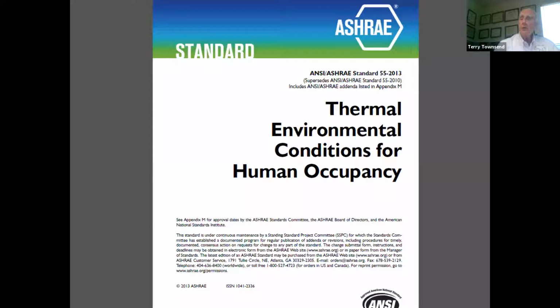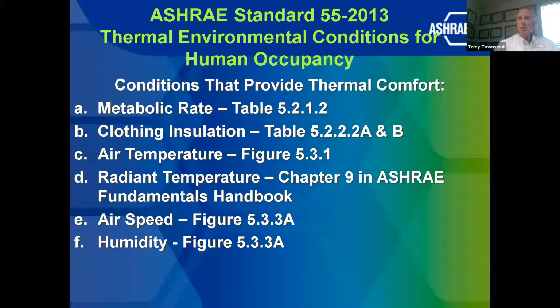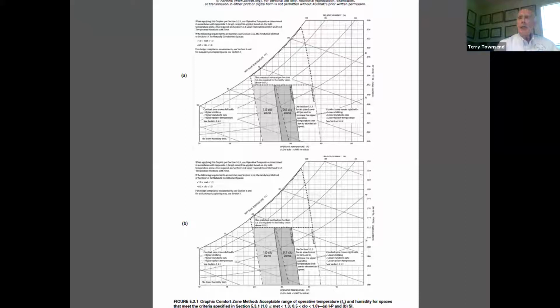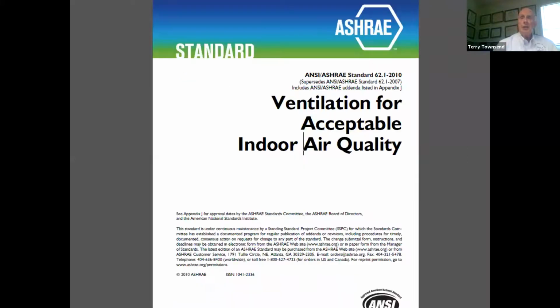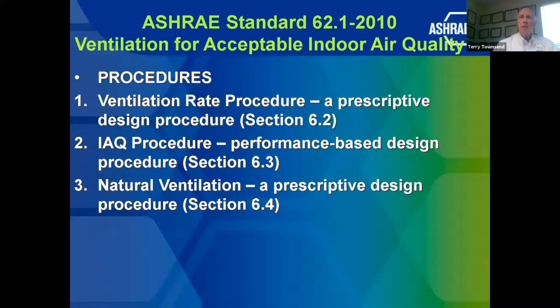First is ASHRAE Standard 55. The tables that you'll be concerned with for the metabolic rate, clothing insulation, air temperature, etc., are listed here. Most of us, I hope, are familiar with these charts that show the comfort levels we are recommended to work between for different temperature and humidity conditions. Standard 62.1 is something that most people, I feel, are familiar with, because it looks at the ventilation rate procedure, which is a prescriptive or cookbook design procedure covered in Section 6.2, the IAQ procedure, and natural ventilation, which is a prescriptive design procedure.